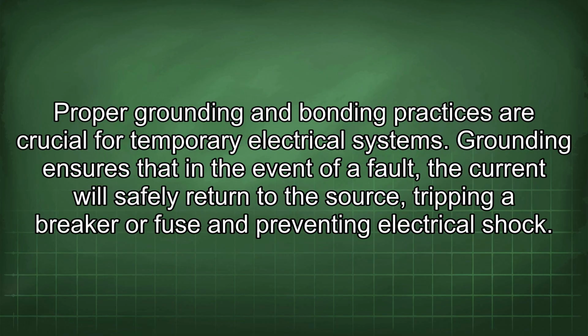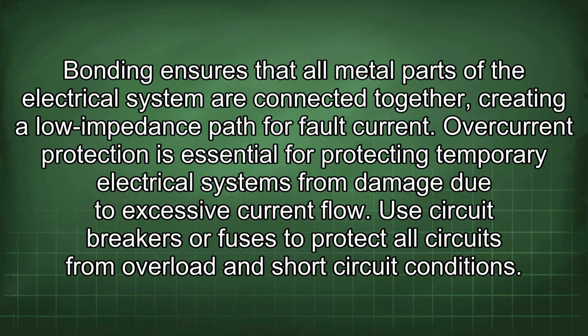Proper grounding and bonding practices are crucial for temporary electrical systems. Grounding ensures that in the event of a fault, the current will safely return to the source, tripping a breaker or fuse and preventing electrical shock. Bonding ensures that all metal parts of the electrical system are connected together, creating a low impedance path for fault current.